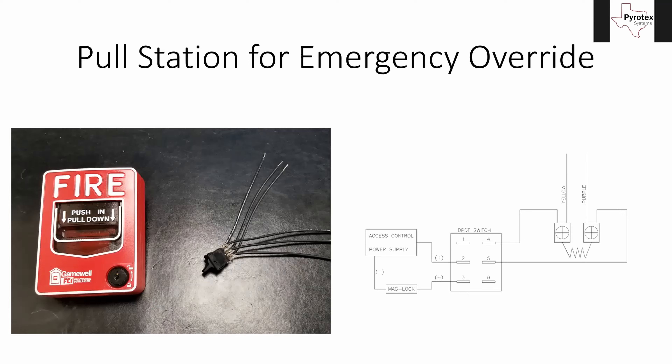A lot of people mistakenly refer to this as a double action pull station, but that's not true. What it is, is a double pole, double throw switch. A double action pull station means you push in and pull down — if it were a single action pull station, you would only pull down without pushing in first. So 'double action' refers to how the pull station is activated, while 'double pole, double throw' refers to what type of switch is in it.